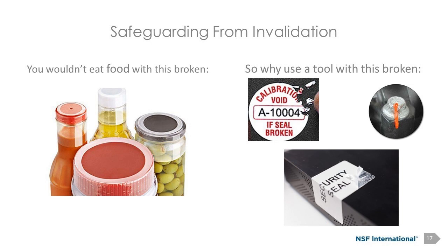And I threw this picture of the foodstuffs on the left because they all have this tamper-evident tape along the top, right? That film, that seal. Would you open a jar that didn't have that or where that was compromised and eat it? Would you drink from a bottle of soda or a bottle of water that had that perforated ring around the top? Would you drink if you saw that broken? I think we're all saying no. So we really shouldn't be using calibrated instruments or verified instruments if these tamper-evident marks or tamper-evident devices are compromised, because we truly don't know if the tool is still good, still valid.